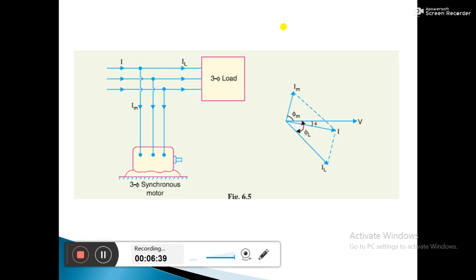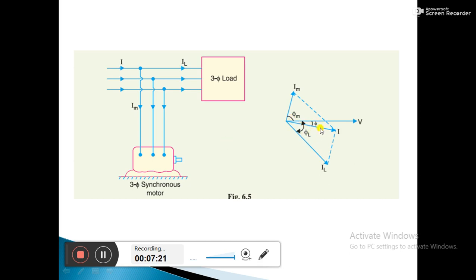In the diagram, the synchronous condenser is connected to the three-phase load. In the phasor diagram, before connecting the synchronous condenser the load current is lagging the voltage. When we connect the synchronous condenser, the motor current leads the voltage. The resultant of the load current and motor current is I. The angle phi before connecting is larger, and after connecting the condenser the angle is reduced, showing improvement in the power factor.